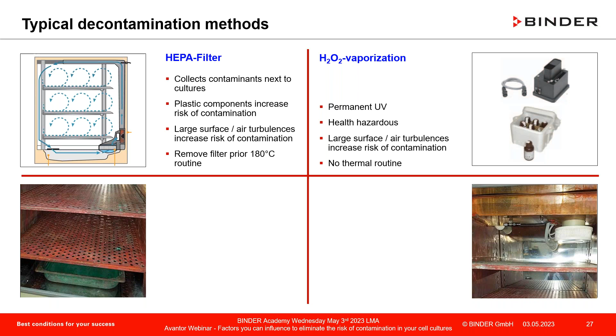Up front, you see a box with 6 little, I think it's 6% H2O2 bottles, 1 bottle per run. If you assume 1 run per month, you need 2 of them per year. We're going to talk about costs, a recurring cost, in just a minute. And the black box in the middle, that is the vaporizer. You pour the content of that little bottle in the vaporizer, and that's how this model works. No thermal routine. Then you have good old copper.